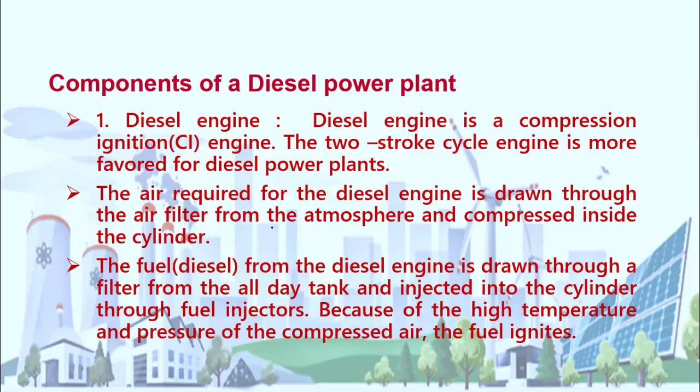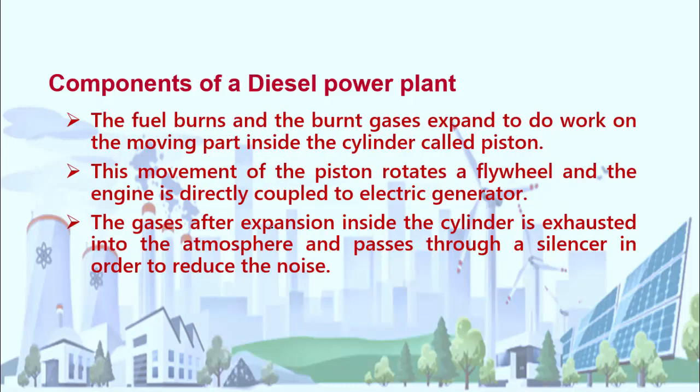The air required for the diesel engine is drawn through an air filter in order to remove the dust particles present in the air. Similarly, the fuel is also filtered through a fuel filter and stored in the day tank, from which it is injected into the diesel engine through a fuel injector, and the fuel and the air get burned, that is, combustion takes place inside the cylinder, and the exhaust gases flow through the silencer to the atmosphere. These are all things we have seen earlier, right?